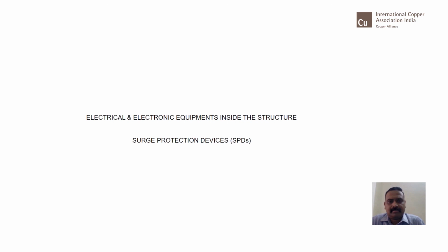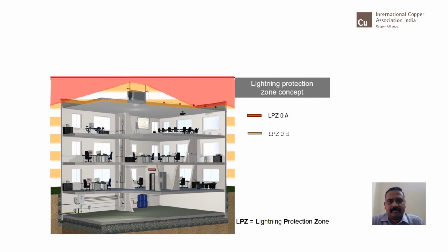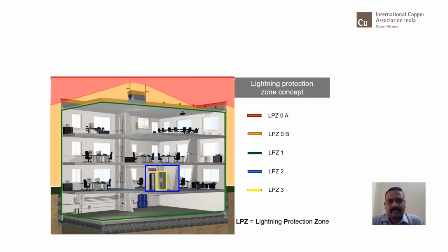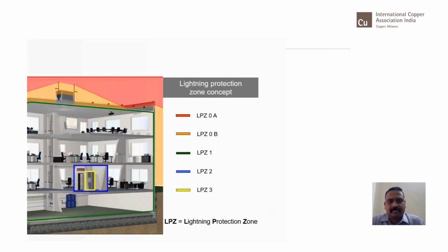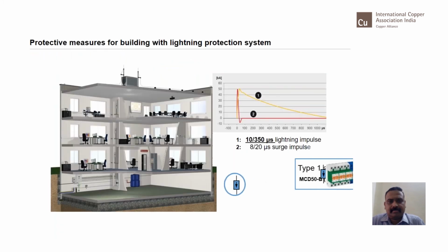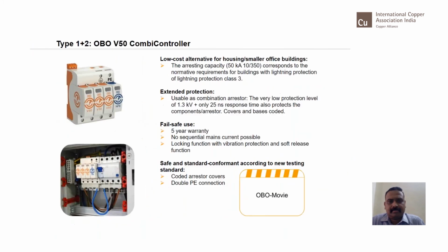The final part of this presentation is about surge protection devices. You have to implement surge protection devices not as one unit at one entry point and say I am protected. No, you need to ensure where all the lightning protection zones of the buildings are and what type of risk can come. For example, will there be a lightning surge which can enter through any of my panels into the building? Will there be any switching surge that will damage my equipment? Will there be any surge that will travel through other services like data, voice or communication? All those lines are to be protected with appropriate surge protection devices. I'm not going to take you through products, however I'll tell you how this is being implemented in multiple places.